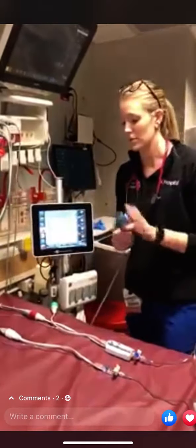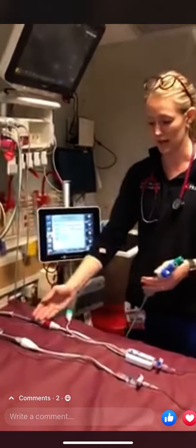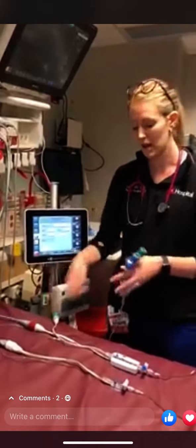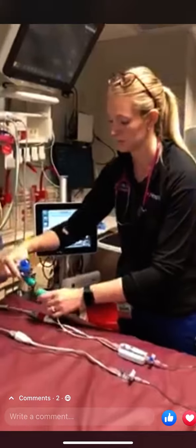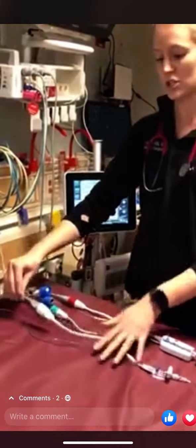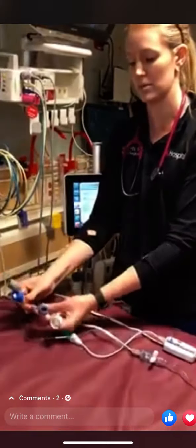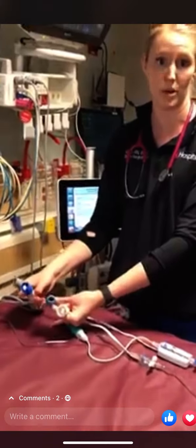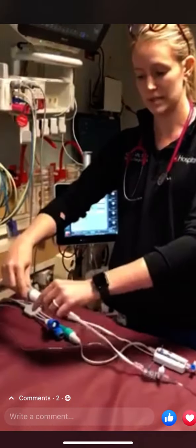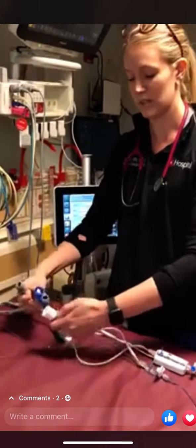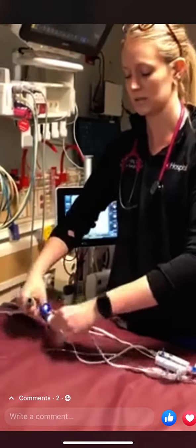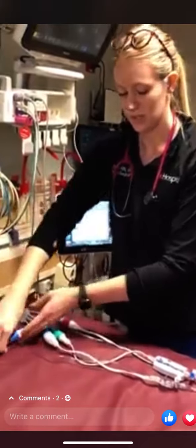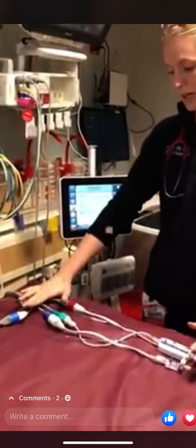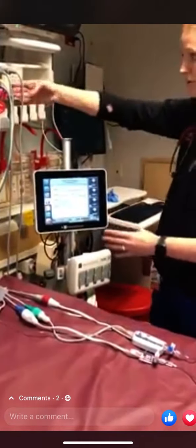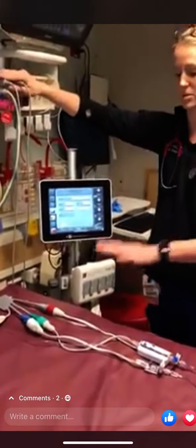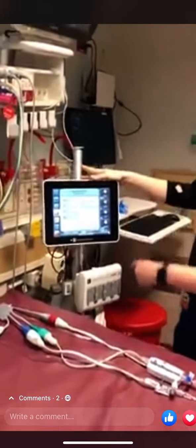So you grab your cables for your EV1000, your arterial line is already set up, your A-line cable plugs into the red port on the FloTrac. From there, you're just going to plug the green into the green, and then you're going to disconnect your CVP setup, which will leave you with 4 cables, right? There's only one possible way to hook these up, so all 4 cables are plugged in. So your normal CVP setup, you break, and then you just connect them where they fit. So you put the male and the female ends together, just like so. Now both your transducers are together. Every single cord here is attached with the EV1000, and both of these cords come back to the monitor. Again, you need 2 pressure cables in order to get this all set up correctly. From there, you just go ahead and set up your EV1000.